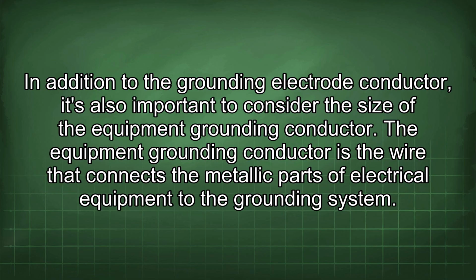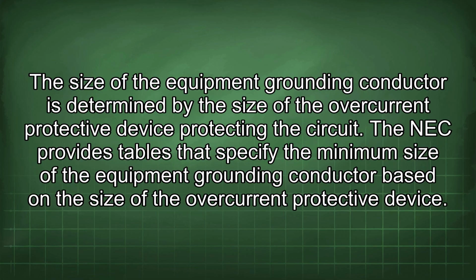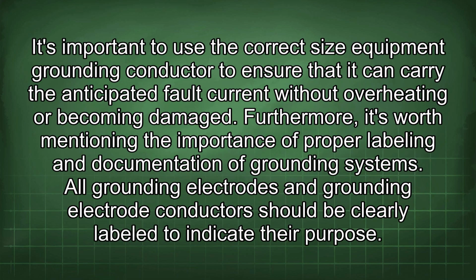In addition to the grounding electrode conductor, it's also important to consider the size of the equipment grounding conductor. The equipment grounding conductor is the wire that connects the metallic parts of electrical equipment to the grounding system. The size of the equipment grounding conductor is determined by the size of the overcurrent protective device protecting the circuit. The NEC provides tables that specify the minimum size of the equipment grounding conductor based on the size of the overcurrent protective device. It's important to use the correct size equipment grounding conductor to ensure that it can carry the anticipated fault current without overheating or becoming damaged.